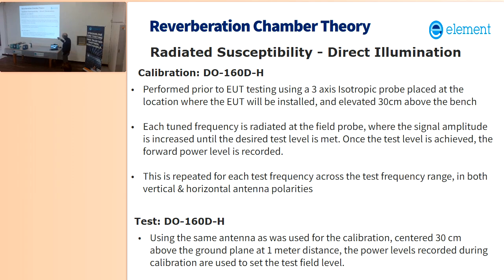So for radiated susceptibility for DO-160, you've got a calibration ahead of time where you put a field sensor out in front of the antenna, crank up the power till you get the field that you want, record that power level, go to the next frequency, repeat, and you do that calibration on an open area of the bench, an empty bench. And then when you run the test, you use that same power level that you recorded and you play it back to run the test with the antenna pointed at the EUT.